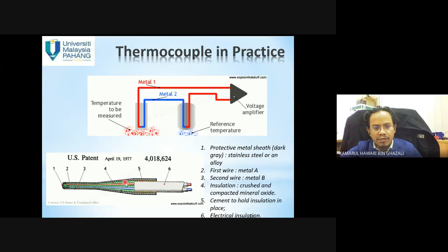So this is an example of a thermocouple, US patent 1977. One is the protective metal shell, dark gray stainless steel. Two, first wire, metal A. Three, second wire, metal B. Four, insulation crushed and compacted. Five, cement to hold insulation. And six, electrical insulation. So this is one type of thermocouple which was patented in the United States in 1977.